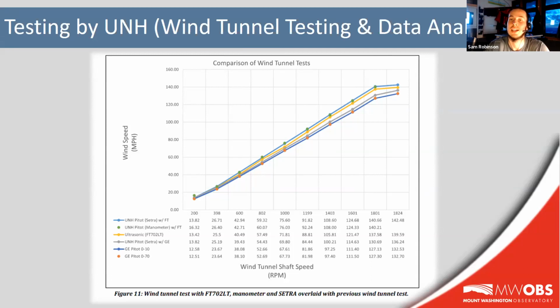I want to stress again that this is actually not as negative as it may seem, as all these instruments are different in design and some difference is expected, especially as wind speed is increased and the 0 to 10 sensors approach those upper limits. This is also the main reason behind that 10% allowable difference, which is set by the World Meteorological Organization.